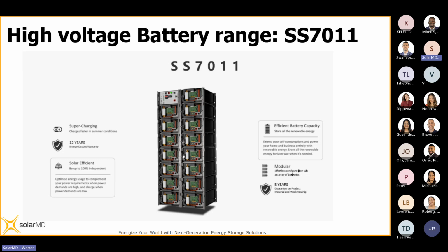If you look at our containerized solutions, where we're dealing with 1 or 2 megawatts of power or megawatt hours worth of storage, we run multiples of these high voltage batteries in parallel. So you can do that too if needed. Of course, the advantage of running high voltage batteries is that you're going to suffer less loss in terms of transmission on the cabling and connectors and so on. It's a lot better to work with.